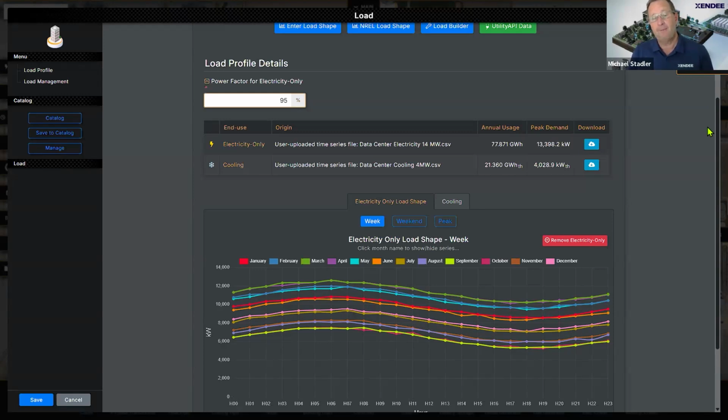And if you have this separated, you have more options in terms of the optimization, because later on, when you optimize the system, you could go to an absorption chiller using some waste heat from a generator to do that cooling, right? So if you lump everything together on the electricity side, then it's not a very smart way to do it because you're reducing the possibilities for you. And this is why we have this differentiation between cooling, heating, and electricity, right? And this is what Rita was pointing out.